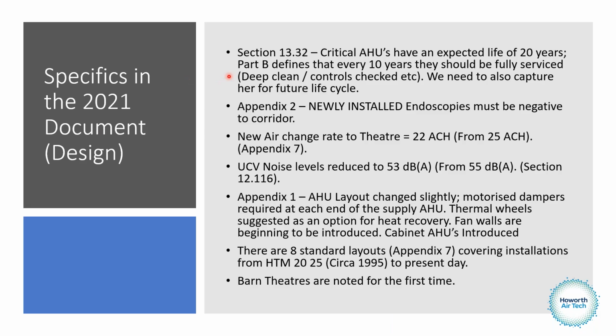A big part of the new HTM is in section 13.32, where critical air handling units now have an expected life of 20 years. This has always been in CIBSE Guide M, but never taken note of really. But now it's in HTM, we have to act on it. Part B defines that every 10 years we should be fully breaking up that air handling unit and giving it a full recommission. That might be nitrogen cleaning coils, stripping it out, replacing the fans and motors, 3 ports off, running them through the full sequence from the BMS, a full deep clean of the AHU at 10 years old.